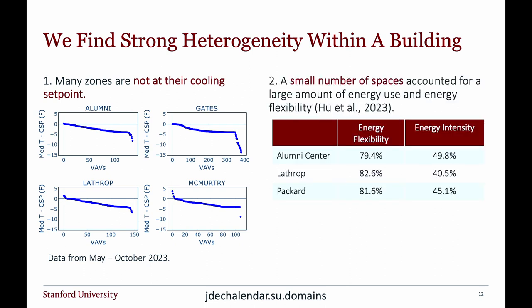A second finding, related to this, is that a small number of spaces - when we ran these experiments, we used models afterward to understand how much energy was being used zone by zone, and how much of the flexibility I measured, like the 30% impact in HVAC, is coming from each zone. What we find is that a small number of spaces account for a large fraction of energy consumption, and another small fraction of zones, not exactly the same set, accounts for a large fraction of the energy reduction. In other words, there's a small number of zones that plays a disproportionate role in determining the building's energy behavior.